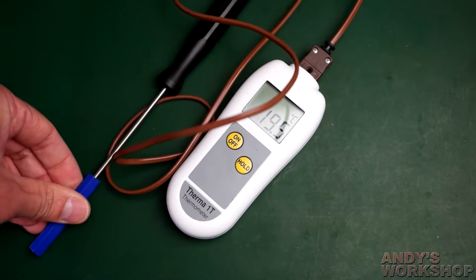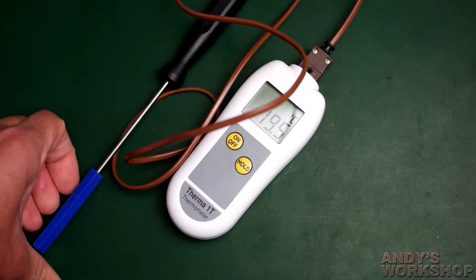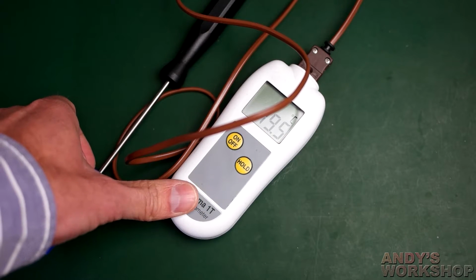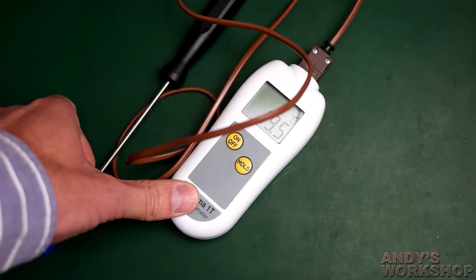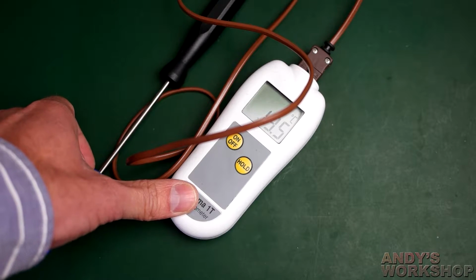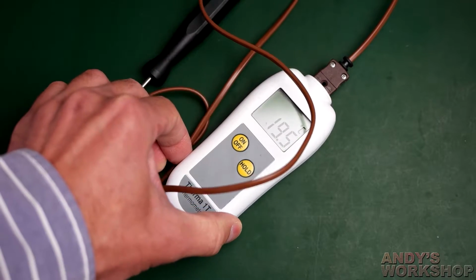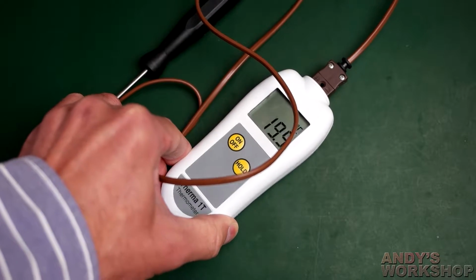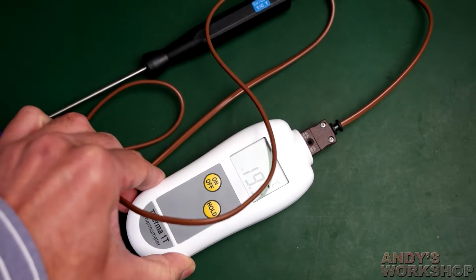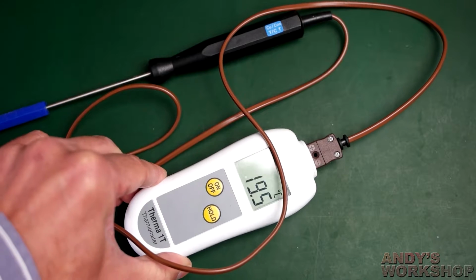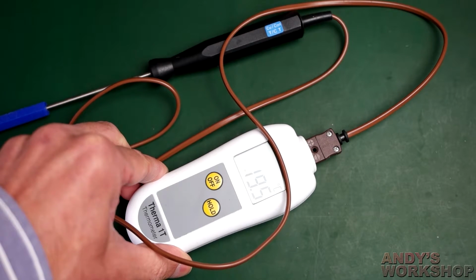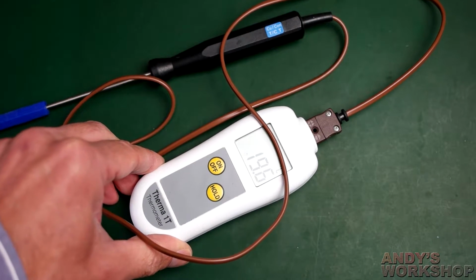It's nice. So if I were to use a thermocouple, I would probably use a T-type, because the standard range of plus or minus 1 degree C is good enough for me. I'd prefer better if I could get it, but that's nice. And since this has been calibrated, I can trust it. But I do have to evaluate the other types of sensors that are available. So let's just take a look at what others there are.